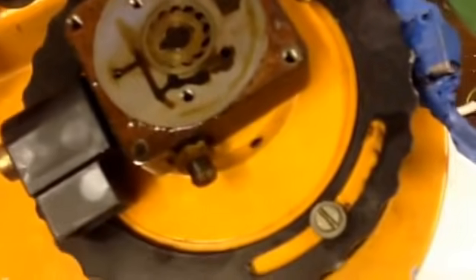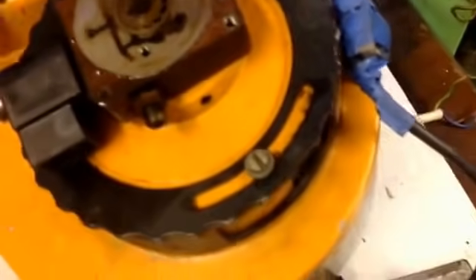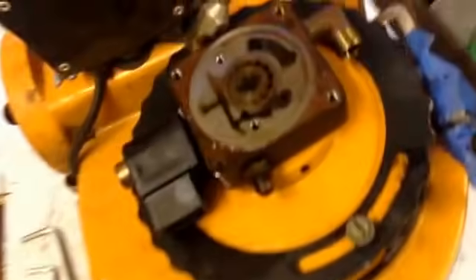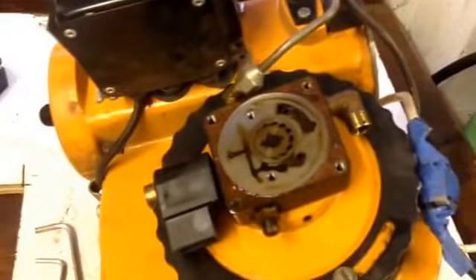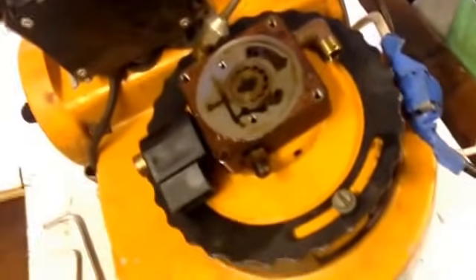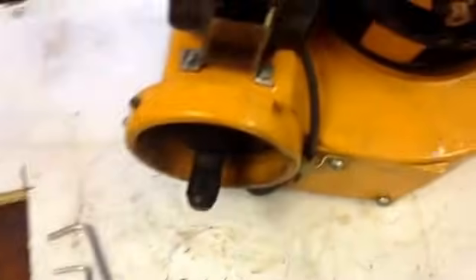Right, commissioning these - you cannot commission one of these really without a flue gas analyzer. You are setting the pump to a certain pressure - normally, just an example, 140 psi or bar or whatever, you'd be setting the pump to. I wouldn't advise touching any of these settings, just because they don't tend to vary too much, so you shouldn't really need to. Other things that go wrong.